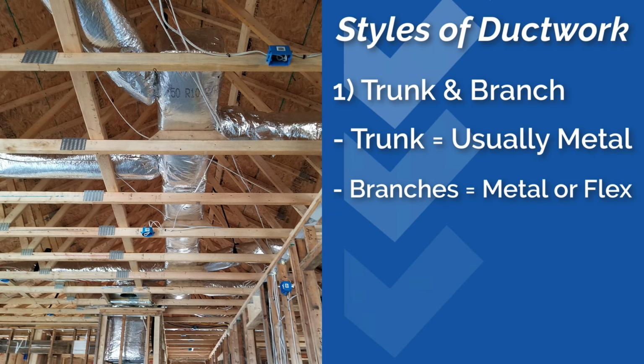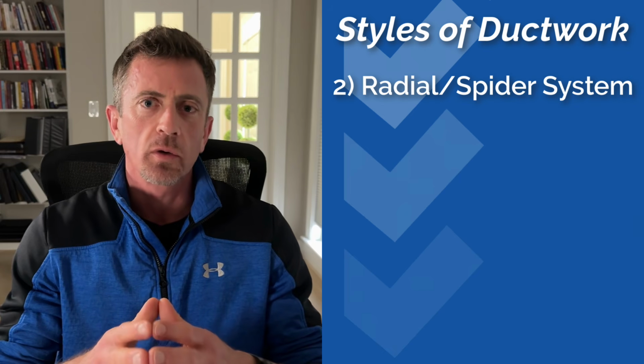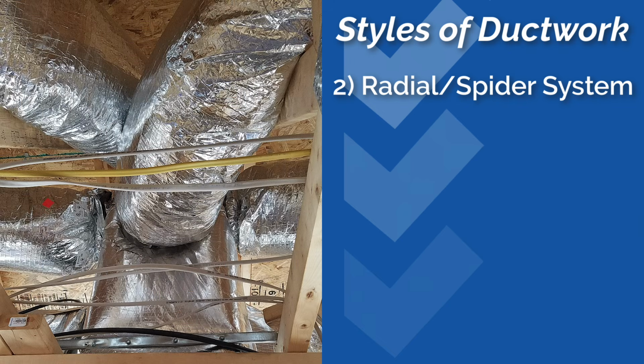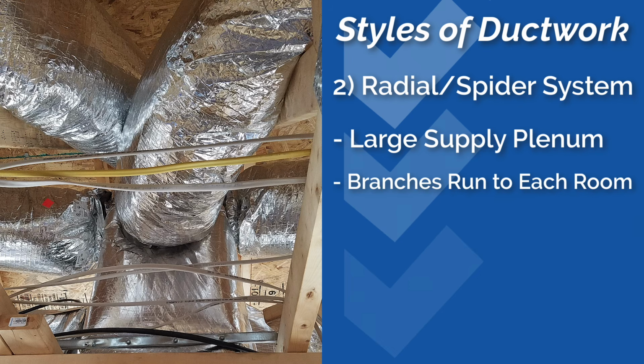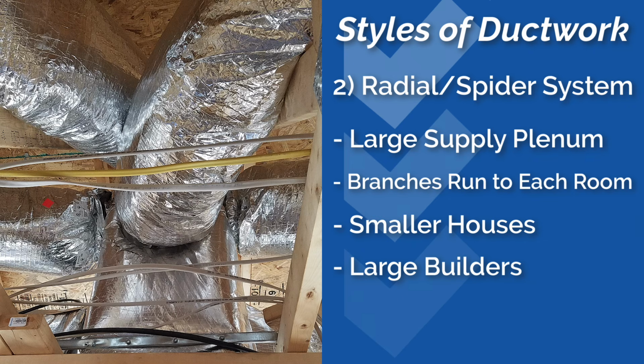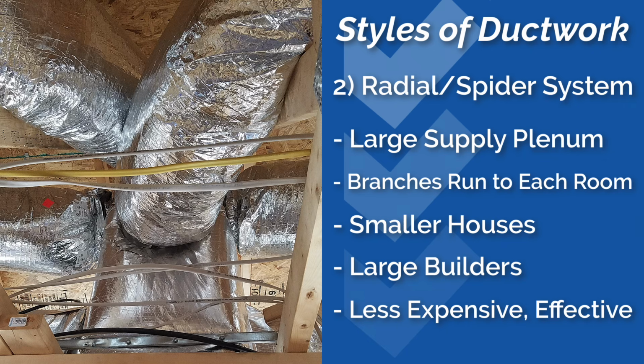The branch ducts can be made of metal or flex ducts, but most homes built since the 1980s will have flex ducts for branches. The second style is called a radial system. This system has a large supply plenum connected to an air handler that connects directly to multiple branch ducts that radiate outward to each room in the house. They're often used in smaller houses and those with open floor plans built by large production builders because they're less expensive to install, but they're usually less effective at distributing air properly as well.